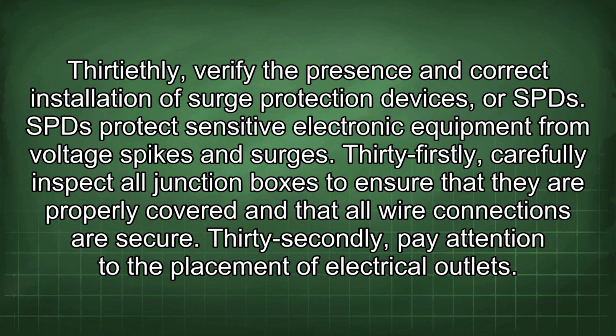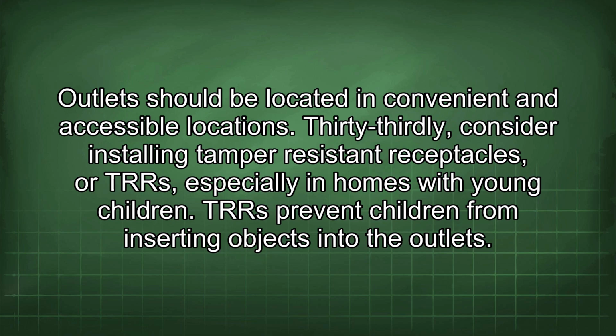30thly, verify the presence and correct installation of surge protection devices, or SPDs. SPDs protect sensitive electronic equipment from voltage spikes and surges. 31stly, carefully inspect all junction boxes to ensure that they are properly covered and that all wire connections are secure. 32ndly, pay attention to the placement of electrical outlets. Outlets should be located in convenient and accessible locations. 33rdly, consider installing tamper-resistant receptacles, or TRRs, especially in homes with young children. TRRs prevent children from inserting objects into the outlets.